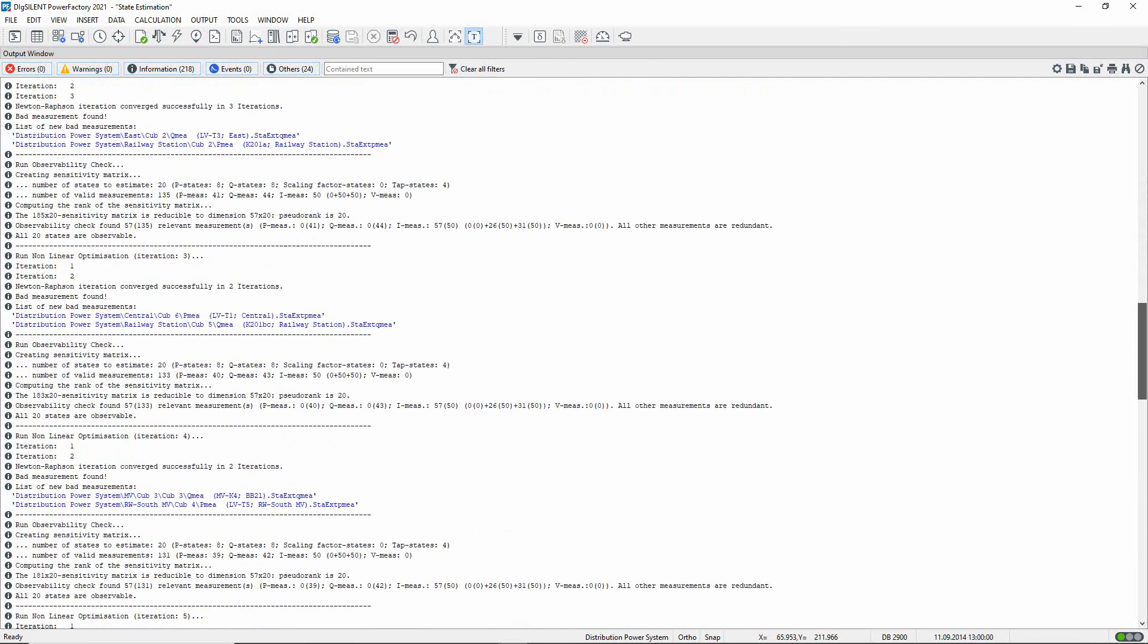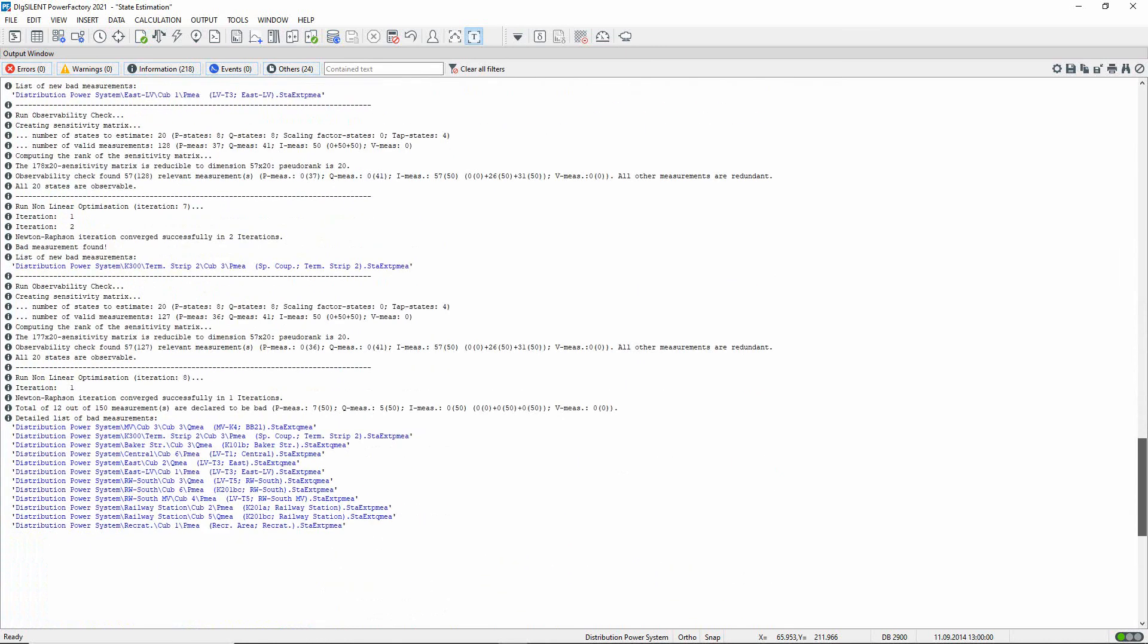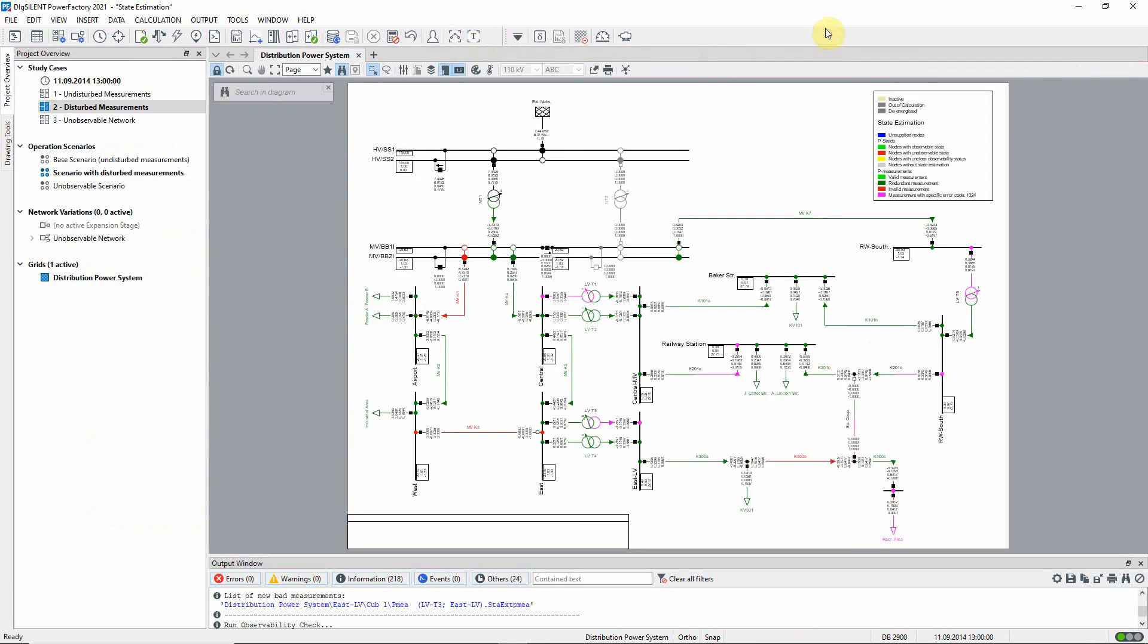Once the plausibility step is completed, the observability check and the state estimation are run in turn in an iterative process. Each iteration allows bad measurements to be detected and replaced by internally calculated set points. These bad measurements which differ from the estimated values beyond the required threshold are listed at the end. In the graphic, the coloring indicates whether bad measurements have been detected.